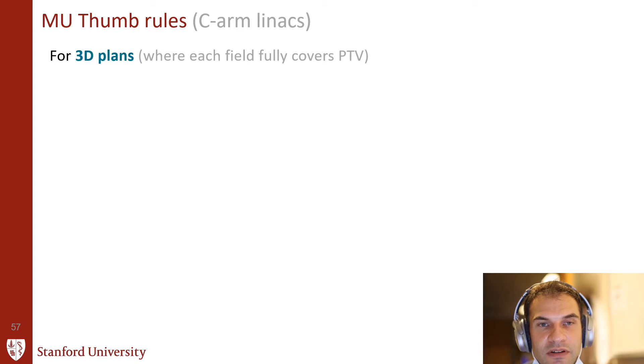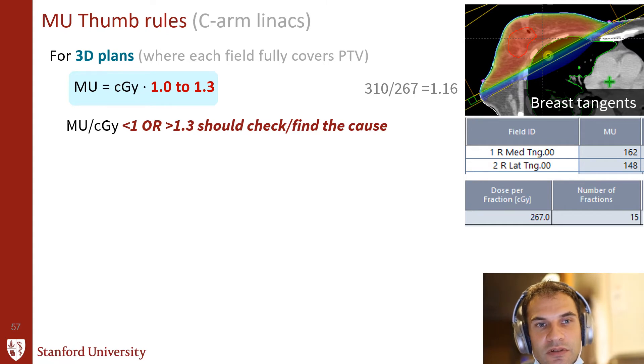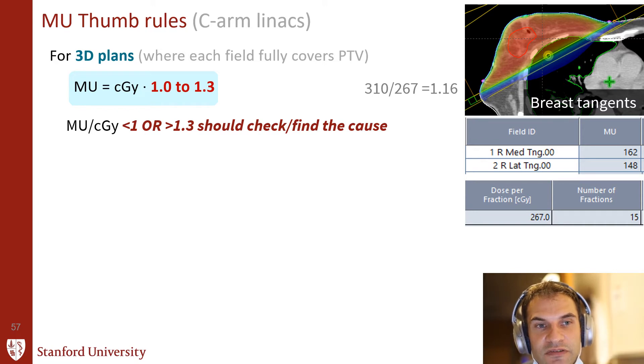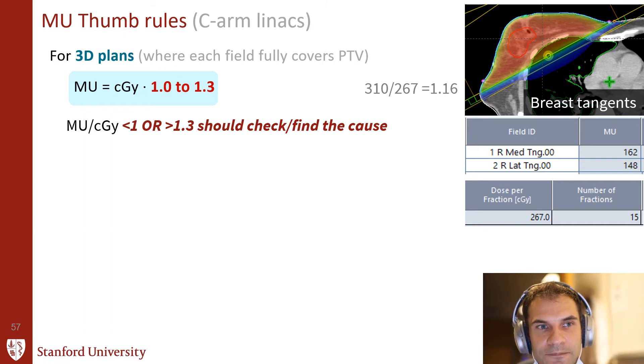Some thumb rules to keep us safe and give general understanding: for 3D plans where each field fully covers the target, such as in breast tangential treatments, the MU and centigray per fraction should be within about 30% of each other. For example, with a breast tangent case delivering 267 centigray per fraction with two fields totaling 310 MU, those values are similar — that's good. If MUs are very different from the dose per fraction in 3D plans, you should check it, as it can be a red flag for a mistake.